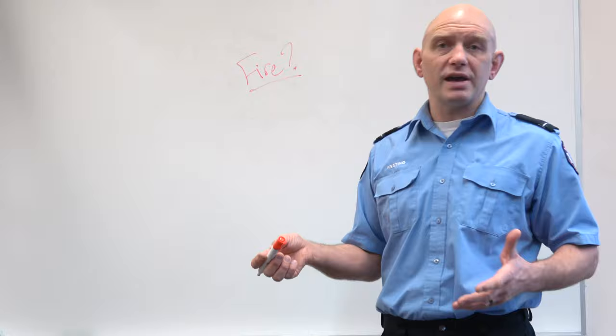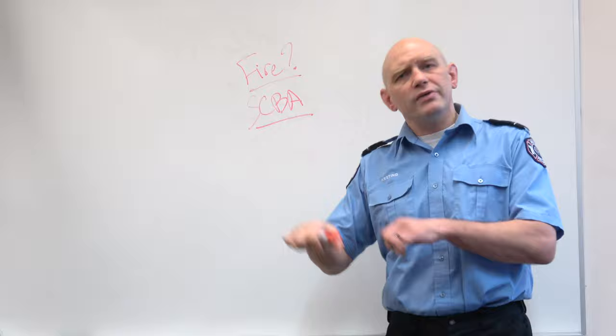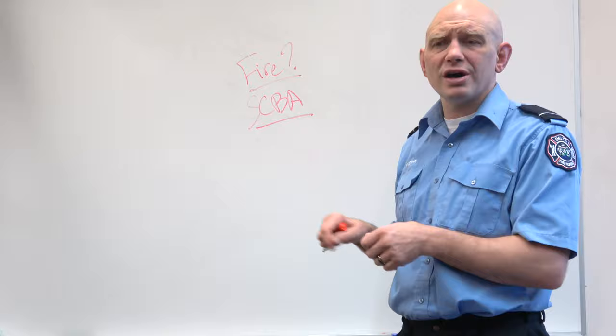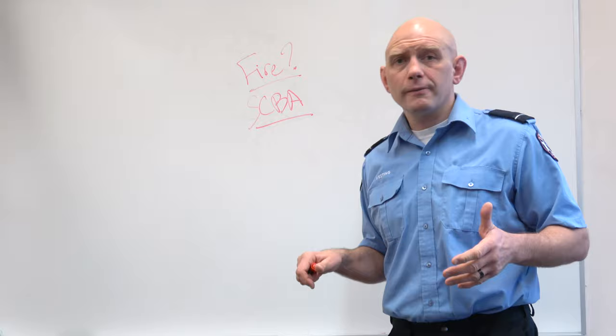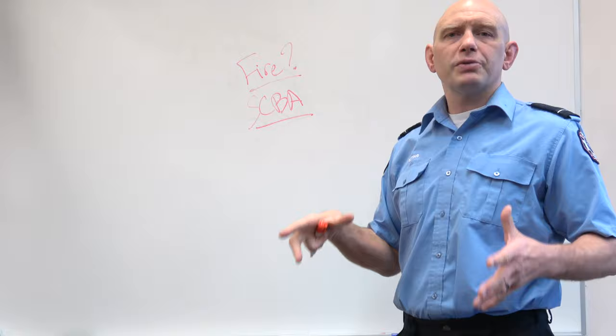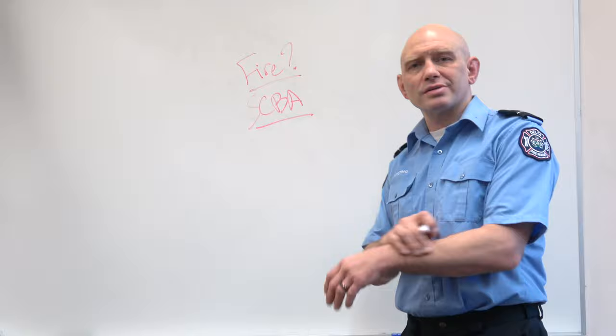Well, now you got to start thinking about the other piece of the puzzle. Fire hazards. Is there a fire or is this flammable? As I said before, Freons generally aren't flammable. But if you heat them up enough, they evolve super poisonous things. You need to know about that. That's if there's a pre-existing fire. Ammonia is poisonous and it's flammable. If there's also a fire in the building or if that ammonia refrigeration plant is threatened by a fire, that's a very different situation from just a leak. You're dealing with a potential bomb. You're dealing with a potential catastrophic hazard.